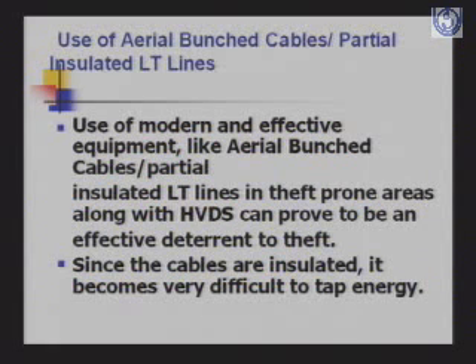You can use aerial bunched cables or partially insulated LT lines. Like we were talking about aerial bunched cables, aerial bunched cables or partially insulated LT lines should be used in theft prone areas along with a high voltage distribution system. One is that you make it a high voltage distribution system, and the LT lines should be aerial bunched cables. It is difficult to tap the cable, so your losses are going to become much less. Instead of bare overhead conductor, you use LT aerial bunched cable for giving supply.